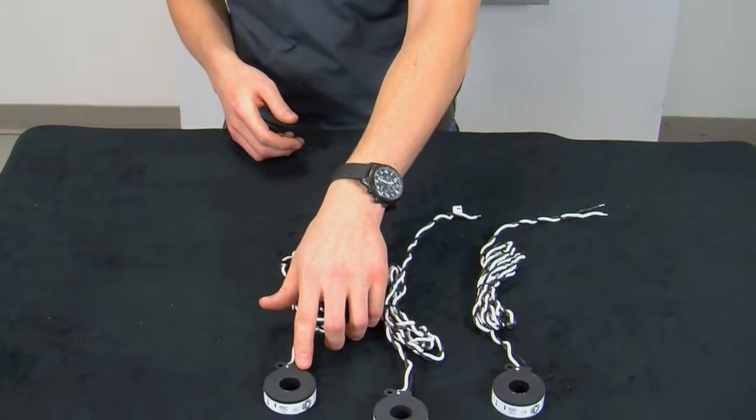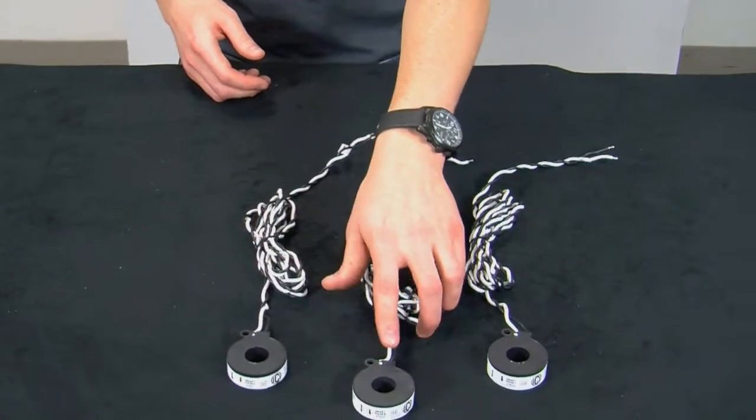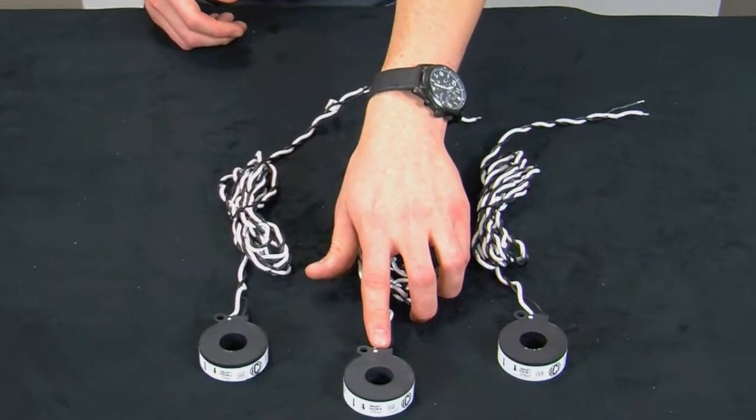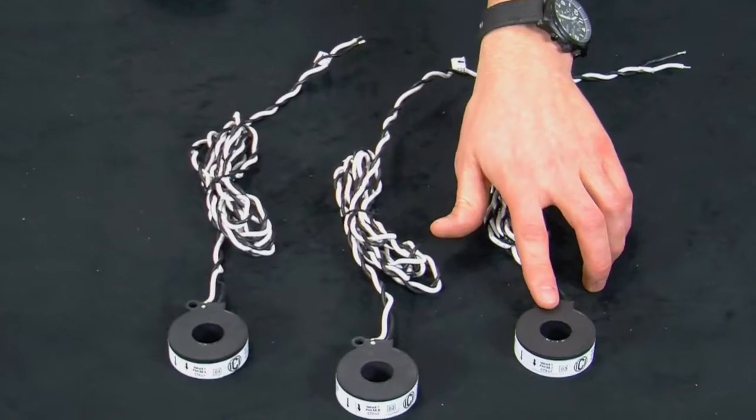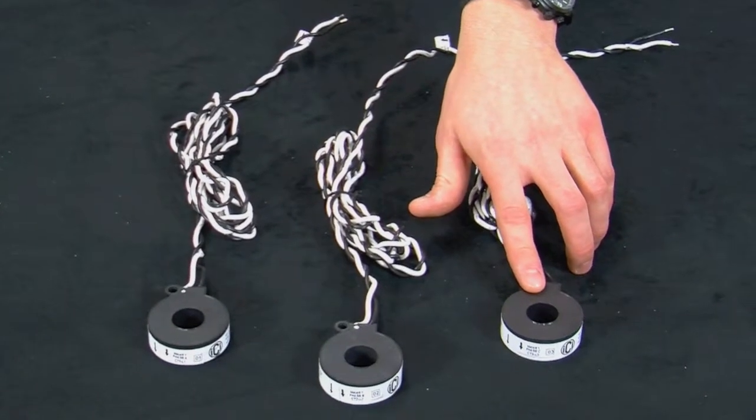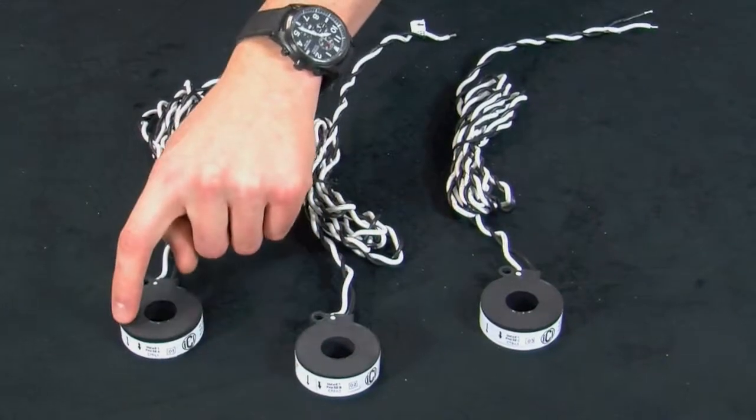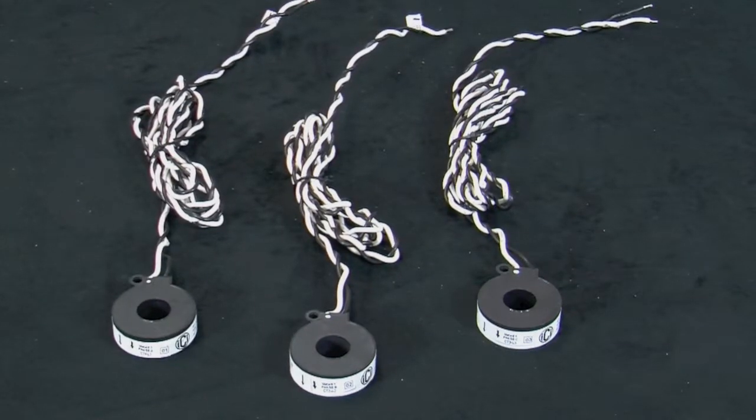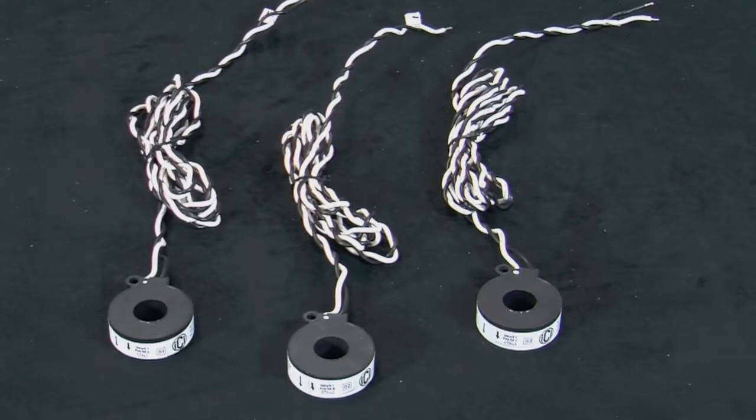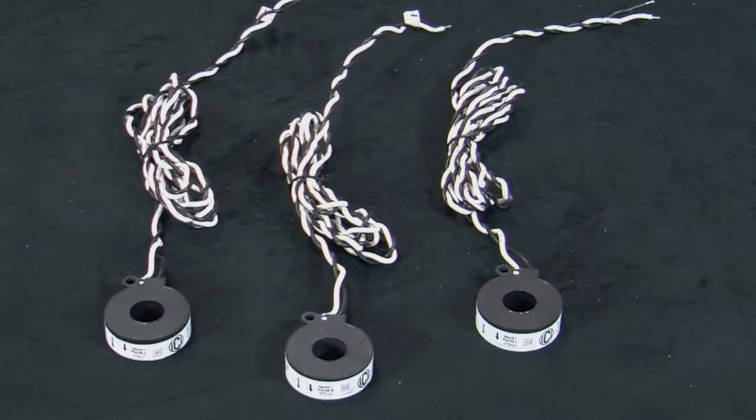CT1 is for phase A or line 1. CT2 is for phase B or line 2. And CT3 is for phase C or line 3. Note the direction arrow on the CTs. This arrow must point in the same direction as the flow of current. So now that we know what each CT is for, let's go ahead and install the CTs.